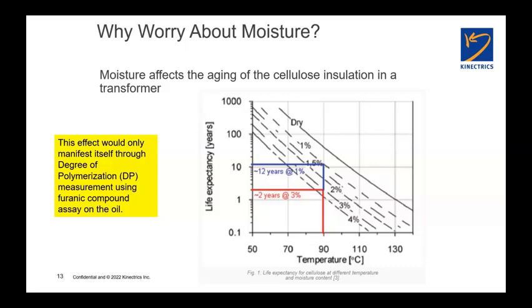Two things that are going along for the ride are the core steel and the paper in the windings. So you really want to be paying attention to making sure your maintenance practices are preserving those two elements as the only two elements that can't be readily replaced. And so when we're talking about paper, again, we're talking about the degree of polymerization of the cellulose molecules in the paper.